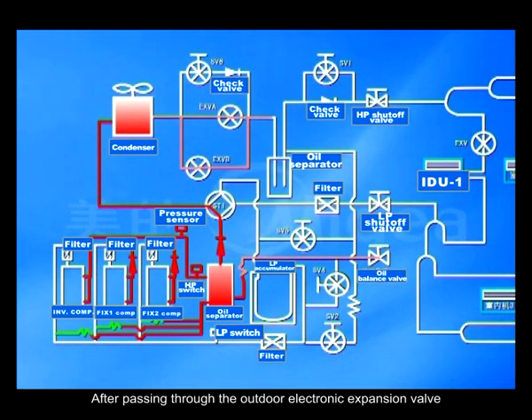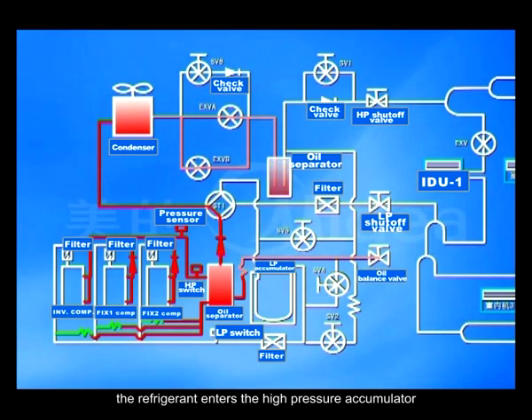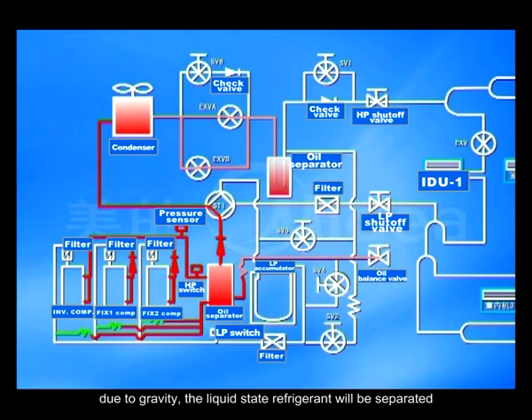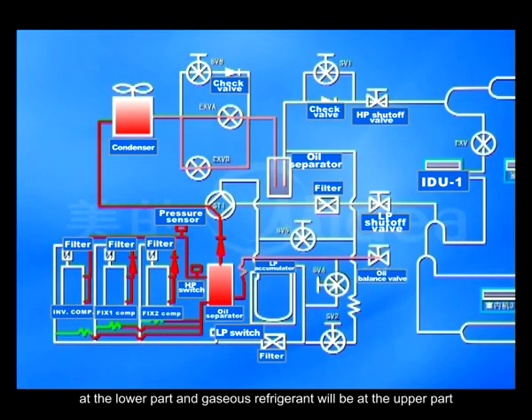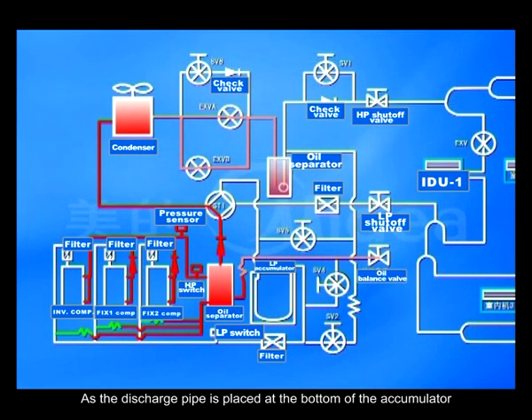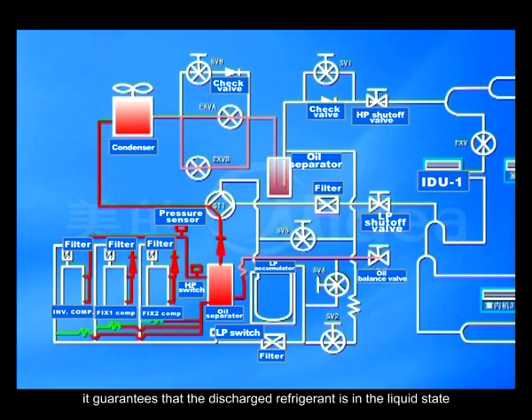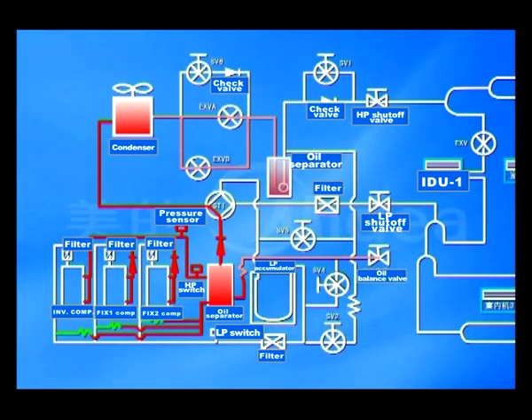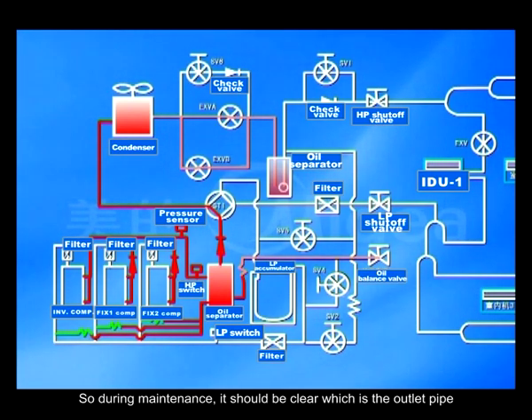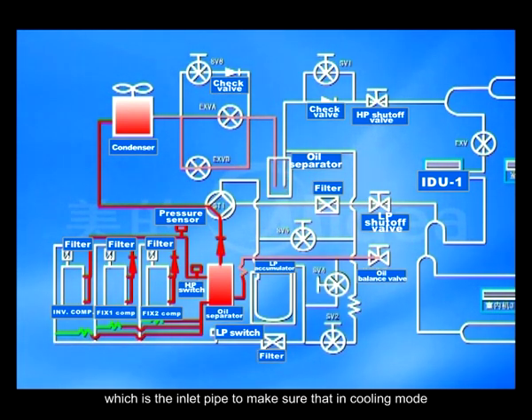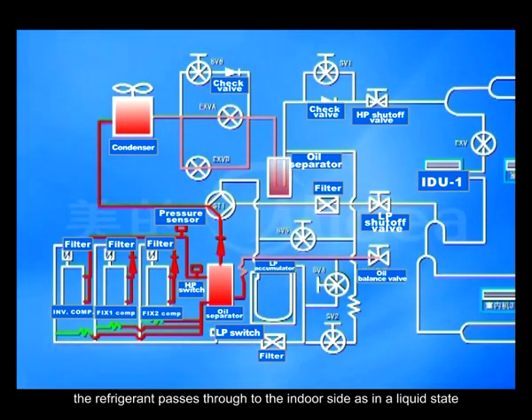After passing through the outdoor electronic expansion valve, the refrigerant enters the high-pressure accumulator. Due to gravity, the liquid-state refrigerant will be separated at the lower part, and gaseous refrigerant will be at the upper part. As the discharge pipe is placed at the bottom of the accumulator, it guarantees that the discharged refrigerant is in the liquid state. So, during maintenance, it should be clear which is the outlet pipe, which is the inlet pipe, to make sure that in cooling mode the refrigerant passes to the indoor side as in a liquid state.